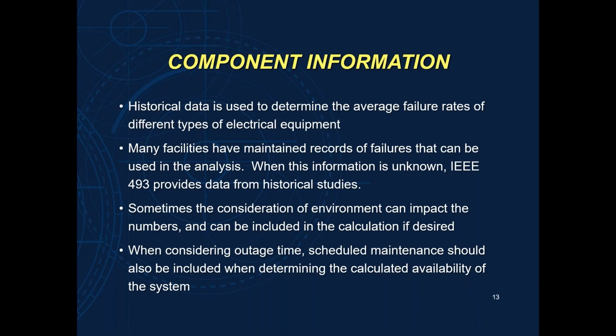Sometimes you might want to consider whether or not you're in a harsh environment, because if you don't have equipment rated for a harsh environment, say a corrosive environment, then maybe your equipment might not last so long. And whenever we're doing one of these studies, we always want to consider scheduled maintenance time as well before we calculate an availability. Keep in mind that when we're giving you an availability value, it's relative to some other study. So we might be comparing two systems to see which one's more available than another.